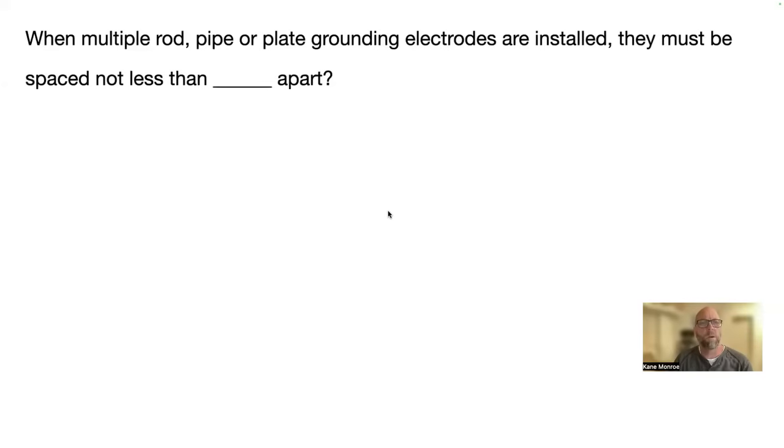All right. When multiple ground rods, pipe, or plate grounding electrodes are installed, they must be spaced not less than blank apart. That is six feet, 250.53 A3.